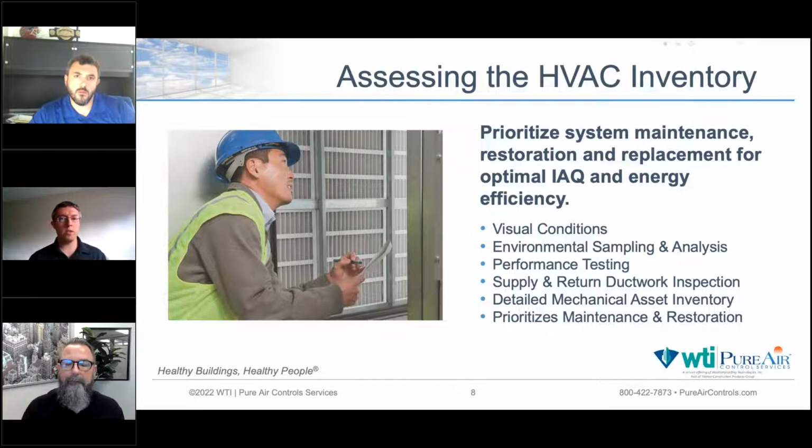And this doesn't just include the air handler, it can include the supply plenum, the return plenum, as I said earlier, ductwork, inline systems, really hitting these air conveyance systems in their entirety. And we use that assessment for each one of these units. We pull together an overall score and report on them and present them. So two things come out of this. There's an overall unit score and then a breakdown of what actually leads to our score and our recommendations.